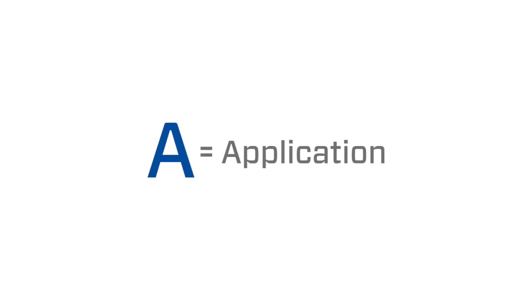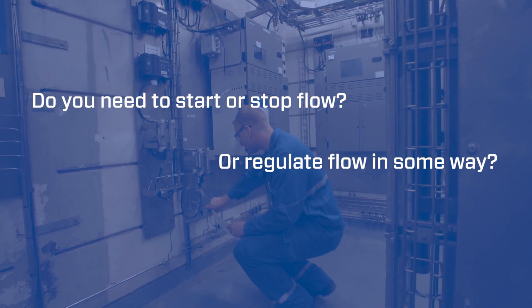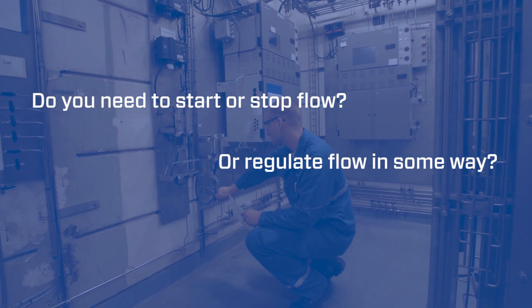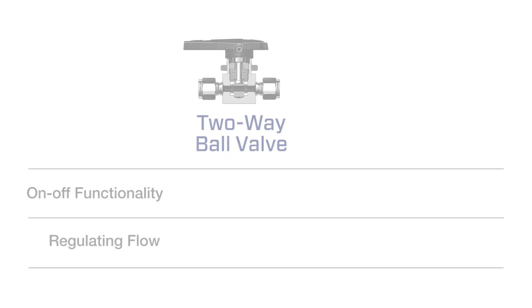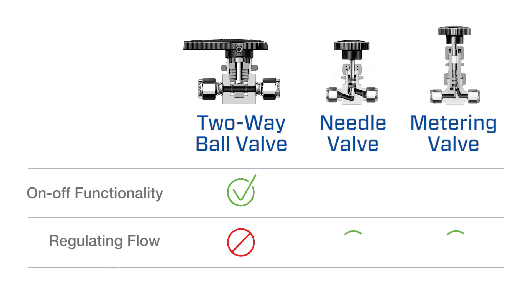Next, think about your application. Do you need to start or stop flow, regulate flow in some way, or control the direction of flow? What about protecting your system from overpressure? A two-way ball valve is a good choice for on-off functionality, but not for regulating flow. If you need to regulate flow, a better option might be a needle or metering valve.